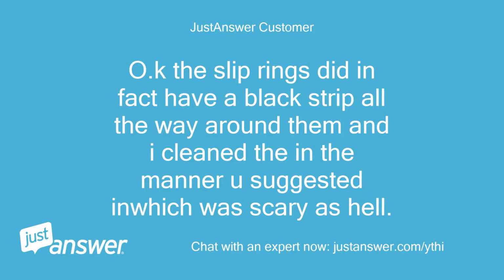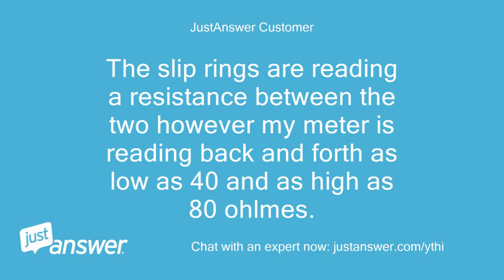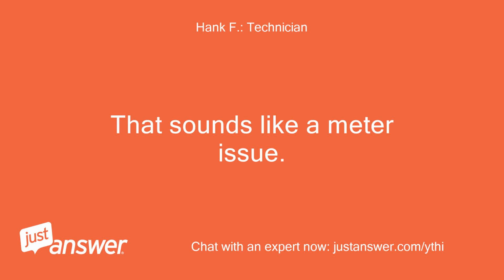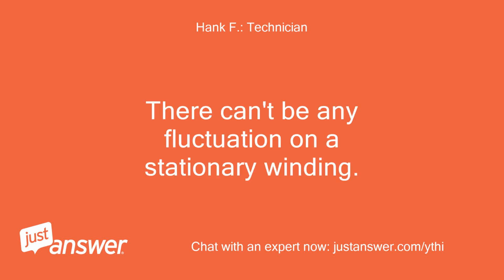Okay, the slip rings did in fact have a black strip all the way around them, and I cleaned them in the manner you suggested, which was scary as hell. The slip rings are reading a resistance between the two, however my meter is reading back and forth as low as 40 and as high as 80 ohms. That sounds like a meter issue. There can't be any fluctuation on a stationary winding.